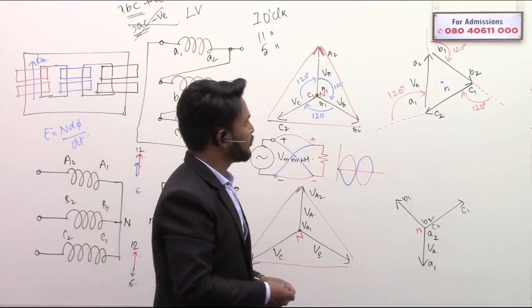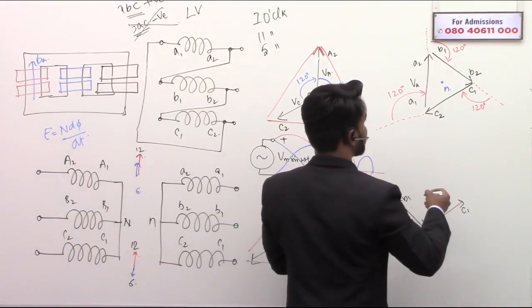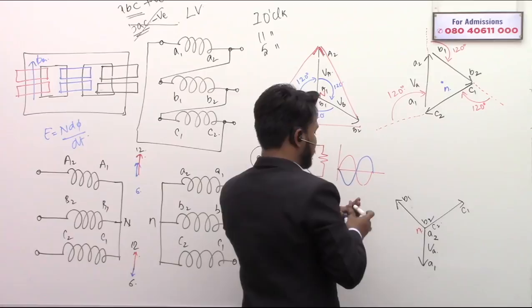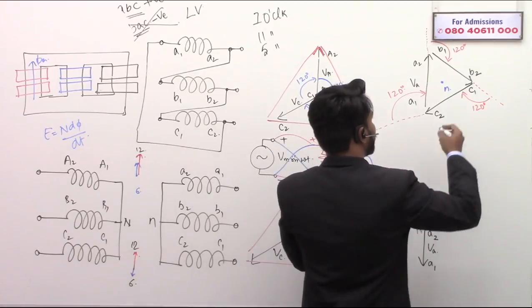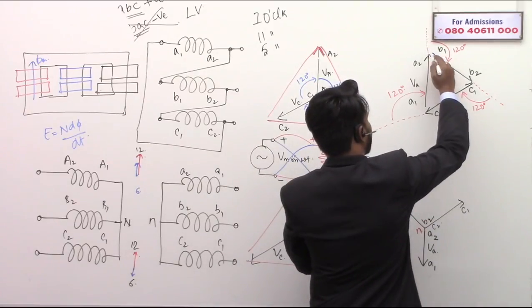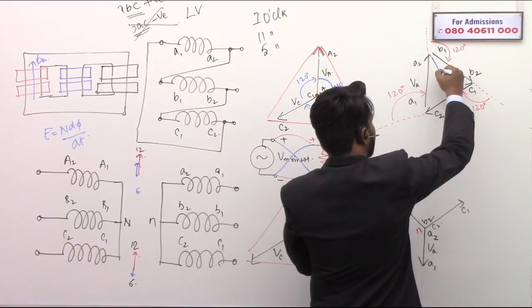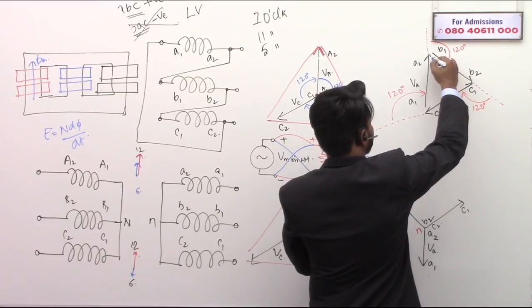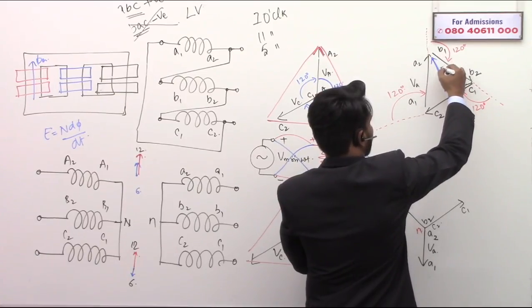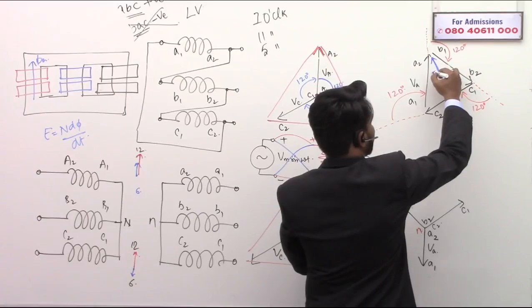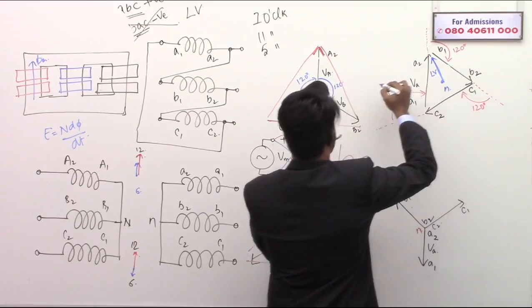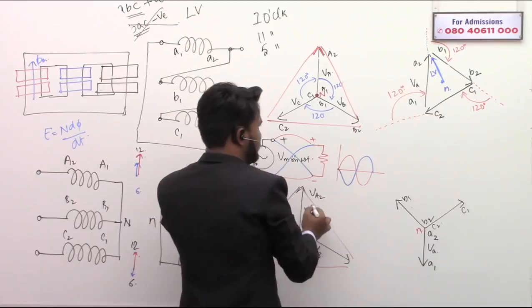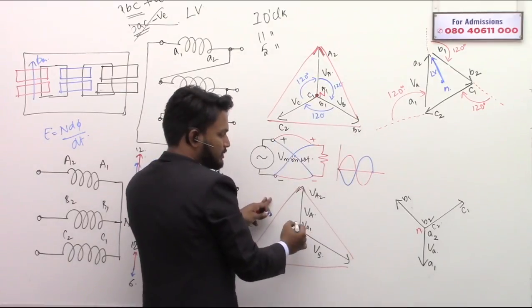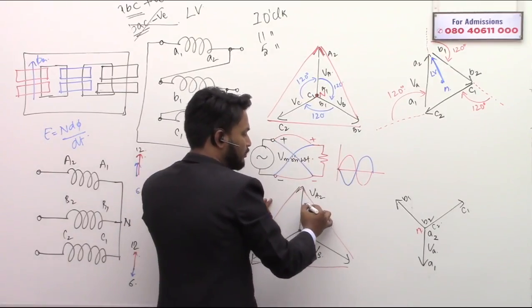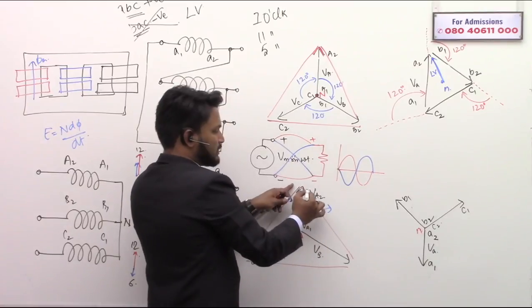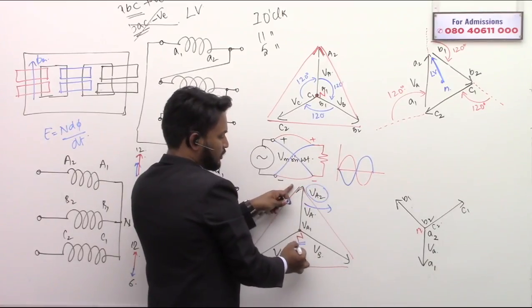So let us look at the phasor groups. The line-to-neutral phasor in the LV side connects A2 to N, yes? This is the line-to-neutral phasor in the LV side. Whereas the line-to-neutral phasor in the HV side got a bit clumsy here, so I'm writing it separately. This is A line and this is neutral.